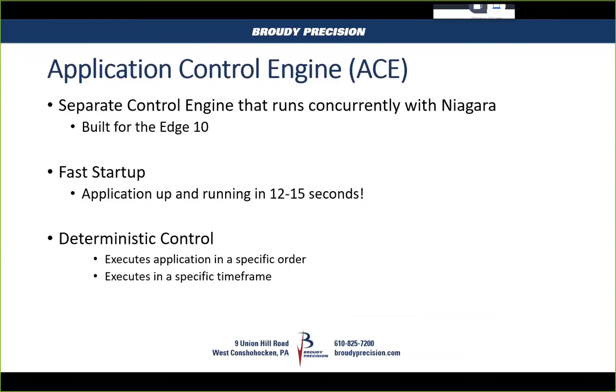I think the bigger piece was that fast startup was a big problem where you've got a large system, like a chilled water system or something. If you have a power bump, you don't have to wait 5 minutes for the Jace to start up to be able to start controlling it, or have the Edge 10 take 3 to 5 minutes to boot up before it starts controlling.